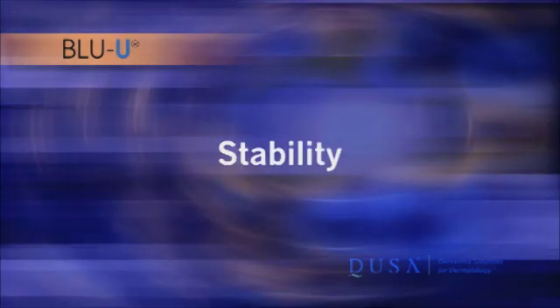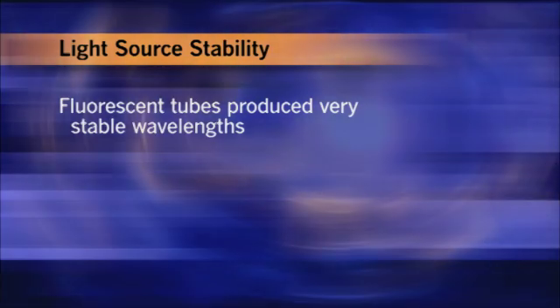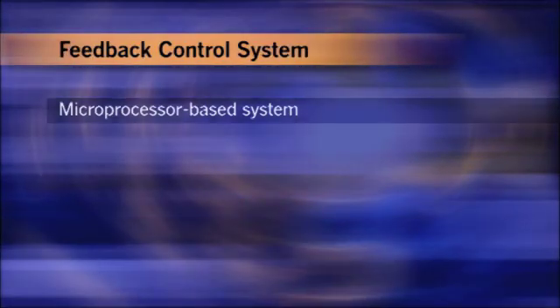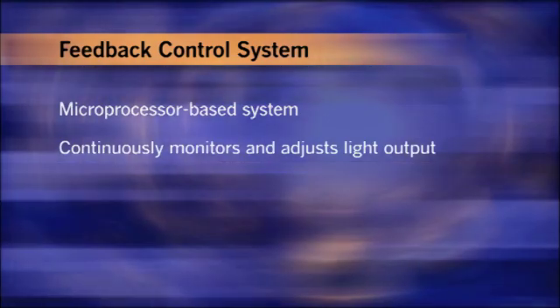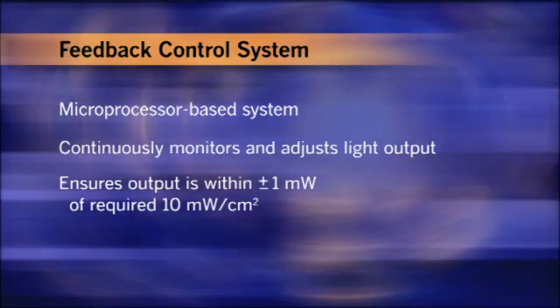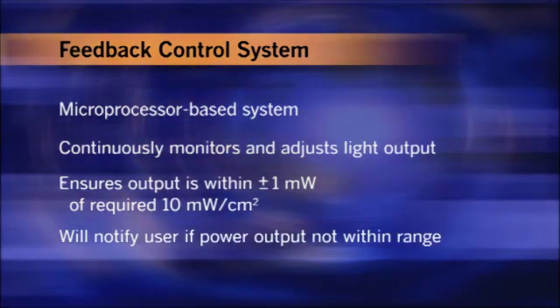To design the BLU-U for the production of blue light and ensure wavelength stability, a wide range of light source technologies was evaluated for both short and long-term stability. Fluorescent tubes produced very stable wavelengths because of the phosphor within the tubes — once a phosphor is chosen, the wavelength is not affected by either temperature or aging. To compensate for any changes in optical power output due to temperature, aging, or local line voltage, we included a microprocessor-based feedback control system that continuously monitors and adjusts light output from the fluorescent tubes, ensuring the BLU-U output is within plus or minus one milliwatt of the required 10 milliwatts per centimeter squared.